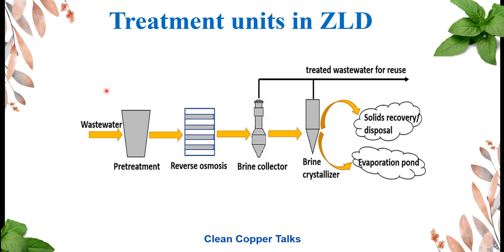In a membrane-based ZLD system using reverse osmosis, pre-treatment involves pH adjustment, softening, or other treatments to make the wastewater suitable for the membrane process. The subsequent steps are the same as in the thermal treatment process.